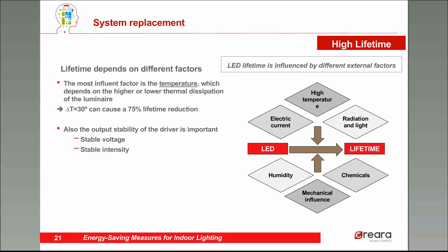Lifespan is determined by the probability of a catastrophic failure and the luminous flux maintenance, because after 60,000 hours the lamp doesn't stop working but the flux weakens. Lifetime depends on different factors — the most influential factor is the temperature, which is the most influential factor in efficiency too. An increase of 30 degrees in temperature can cause a 75% lifetime reduction. Also important is the output stability of the driver — we need a stable voltage and stable intensity. Other factors include radiation, humidity, mechanical influence, and chemicals.